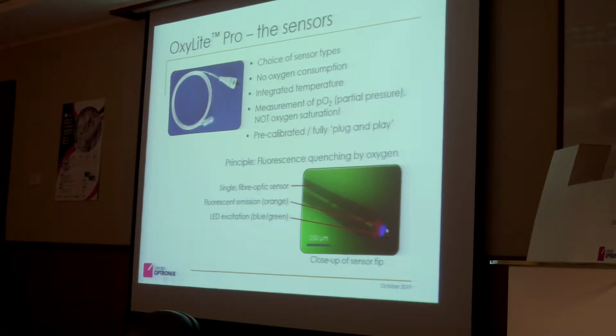Now we have a greenish instead of blue light coming out of the glass fiber to the sensor tip. It excites the electrons on the phosphorescent dye, which jump to a different energy level. And when the electrons jump back, they emit orange light. And the orange light goes back through the same glass fiber to the machine and is detected. So if you have no oxygen there, the orange light might last about 3.5 microseconds. If you have 10% oxygen there, the lifetime of the light is shortened, is quenched, and you might just have 1 microsecond.